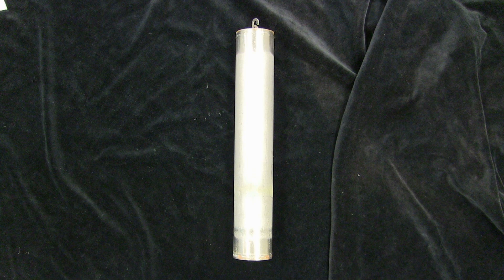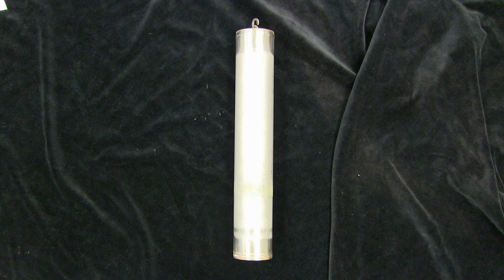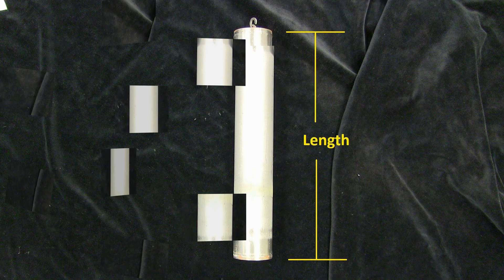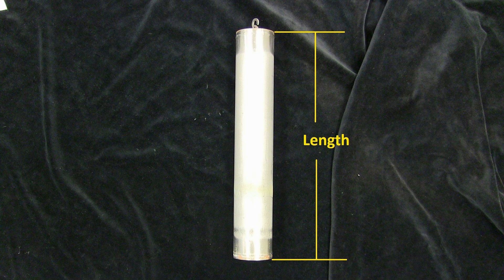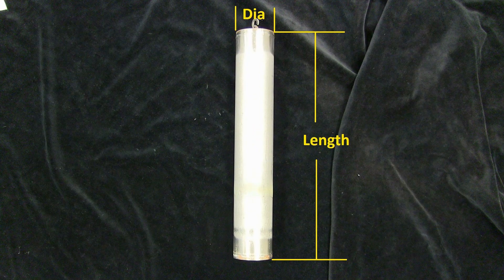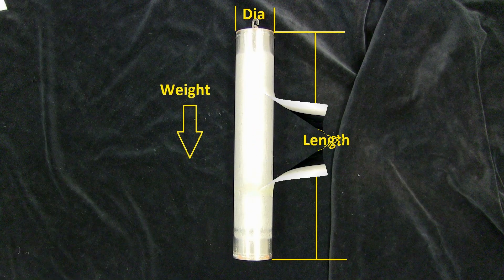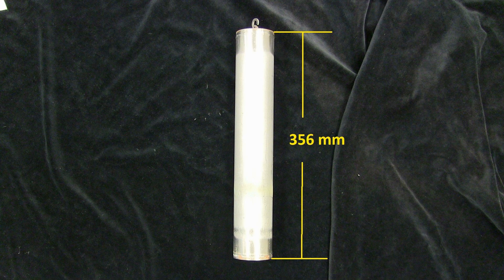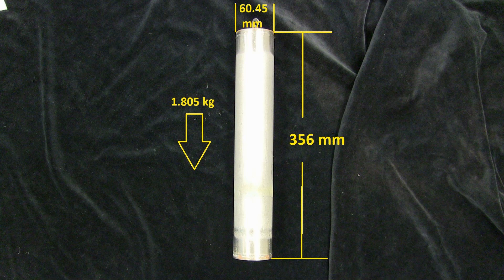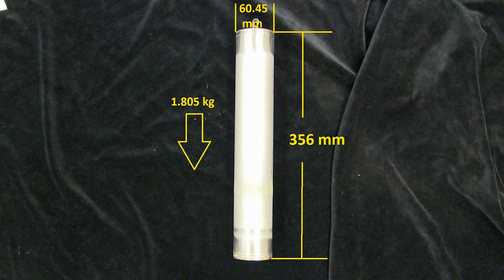Prior to configuring the transmitter, it is necessary to have the required information relative to the displacer being used. The required data is displacer length, diameter, and weight. In this demonstration, we are using a displacer with a length of 356 millimeters, a diameter of 60.45 millimeters, and a weight of 1.805 kilograms.